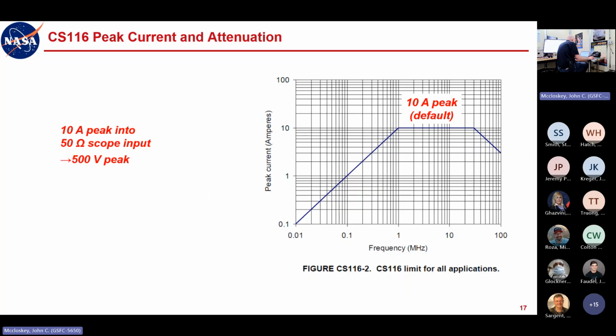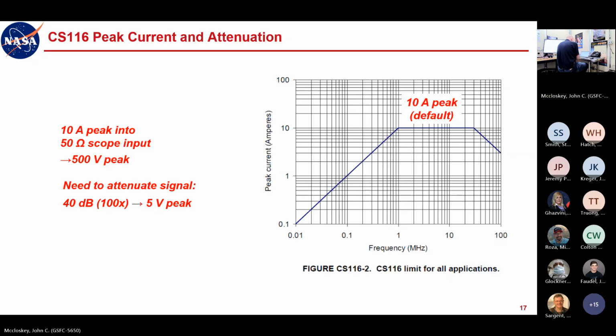A 10 amp peak into a 50 ohm scope input, that's going to give you a 500 volt peak. So there again, not something you want to do directly. So you want to put some attenuation in line with that. 40 dB or a factor of 100 will knock that down to a 5 volt peak. And that's what I'm going to show here. That'll be right at the edge of what we can observe, because with the 50 ohm input, this scope will limit you to a plus or minus 5 volt range.